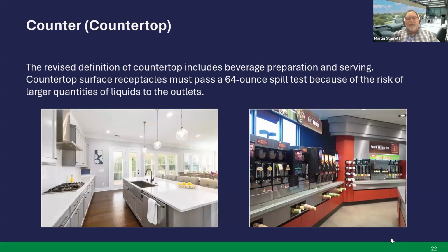Countertop. The definition for countertop was revised to include beverage preparation and serving. Also, you have some informational notes that carry you to the listing requirements, and basically a countertop surface receptacle must pass a 64-ounce spill test because of the risk of the larger quantities of liquids to the outlets. So a lot of these receptacles that you put in the countertops, embedded in the countertops, will have to be listed for this purpose because they have to meet that requirement. We'll get into that whenever we get into chapter 4. Next slide.